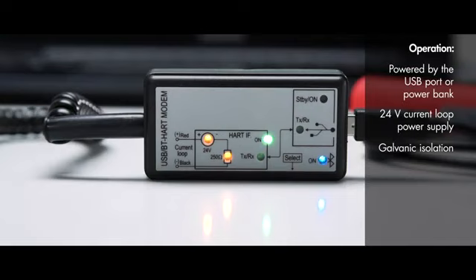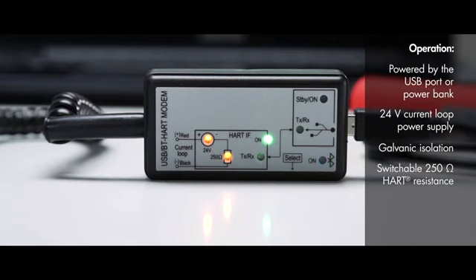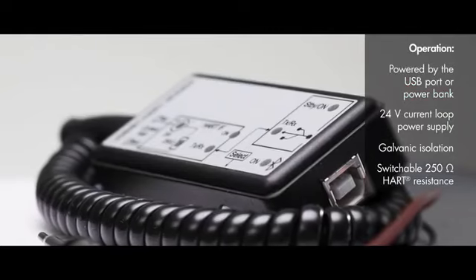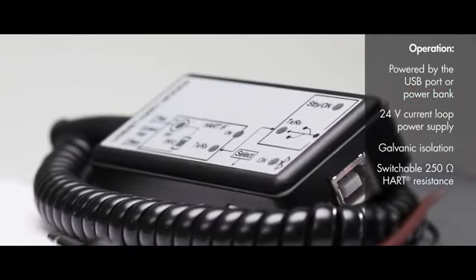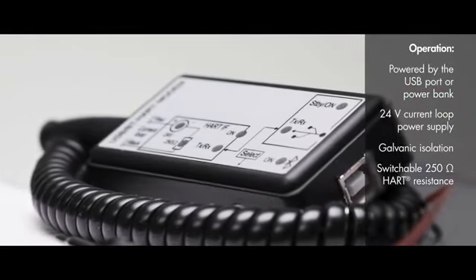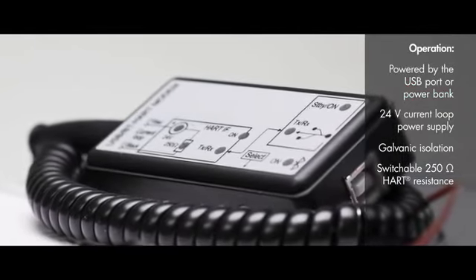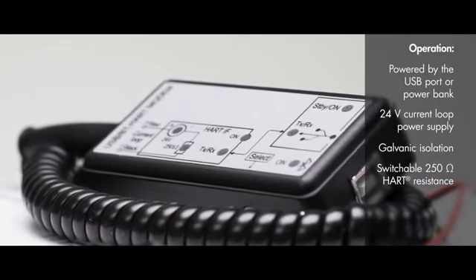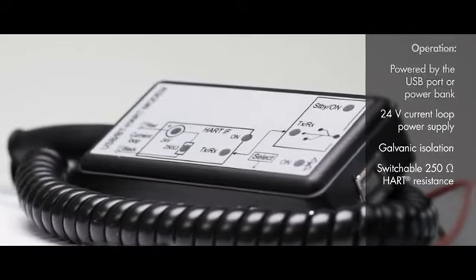The 24-volt DC transmitter supply option can be switched on and off on the device. Another practical feature of the device is that it includes a built-in switchable 250-ohm HART resistance.